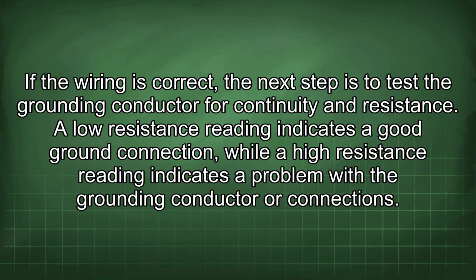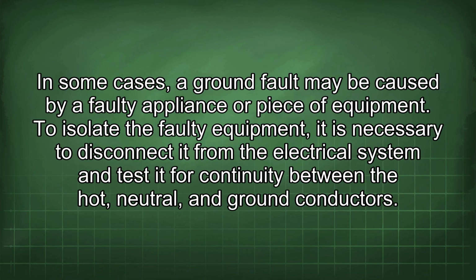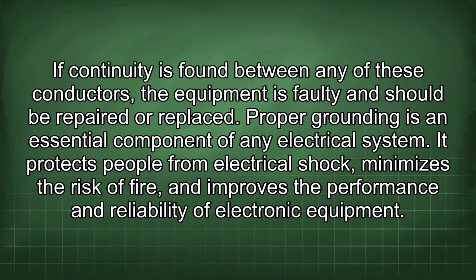grounding conductor or connections. In some cases, a ground fault may be caused by a faulty appliance or piece of equipment. To isolate the faulty equipment, it is necessary to disconnect it from the electrical system and test it for continuity between the hot, neutral, and ground conductors. If continuity is found between any of these conductors, the equipment is faulty and should be repaired or replaced.